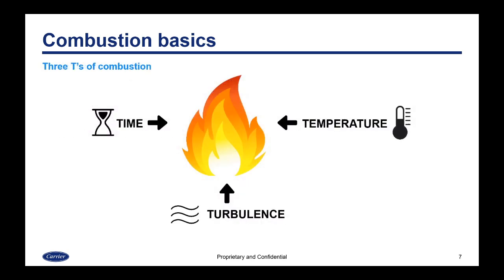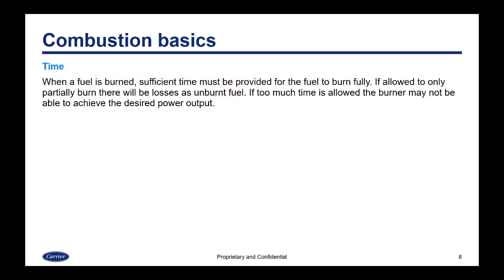With combustion there are three T's: time, temperature, and turbulence. For the first T — time — when a fuel is burned, sufficient time must be provided for the fuel to burn fully. If allowed to only partially burn there will be losses as unburnt fuel, and if too much time is allowed the burner may not be able to achieve the desired power output.